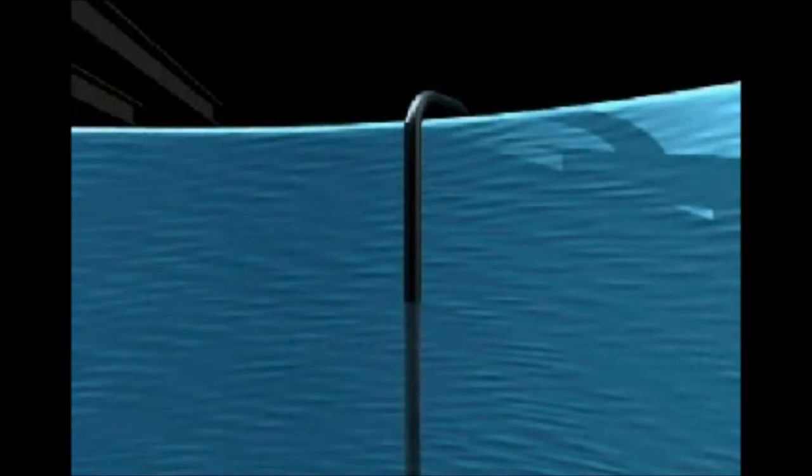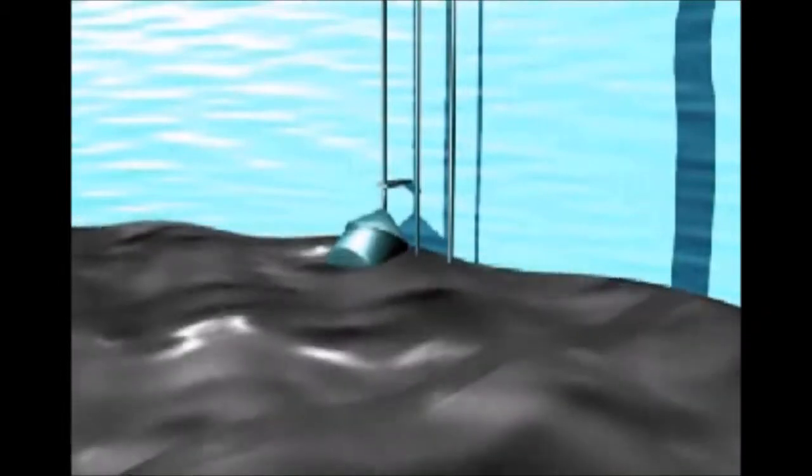Upon the starting of a batch treatment, the equalization transfer pump transfers the wastewater to the treatment tank. On reaching the high-level sensor in the treatment tank, the equalization transfer pump automatically stops. The same signal begins the treatment process, starting the treatment tank mixer and the recirculation of wastewater in the treatment tank.